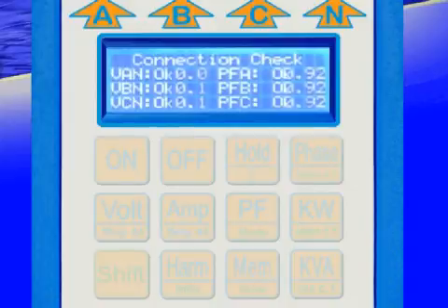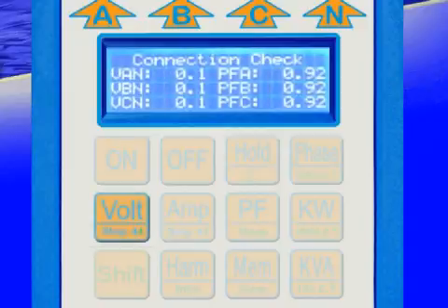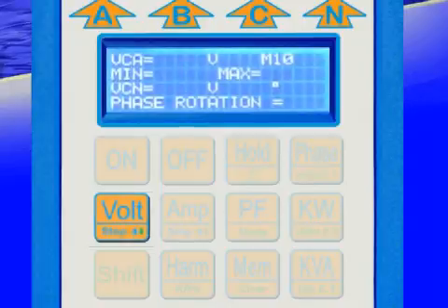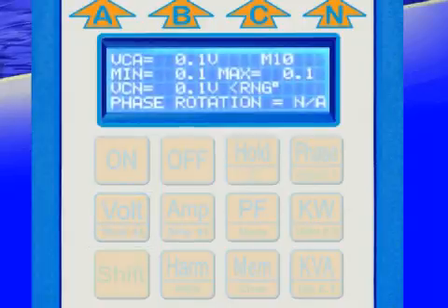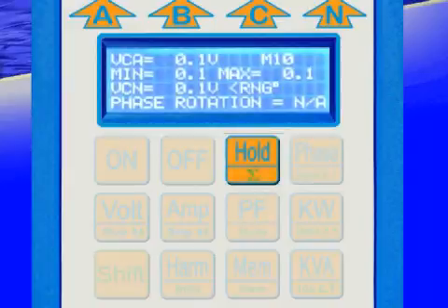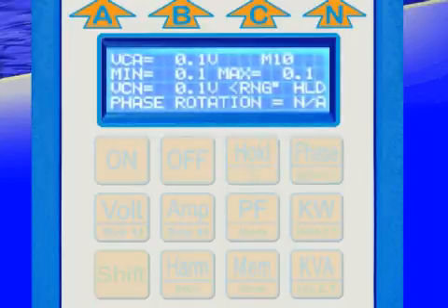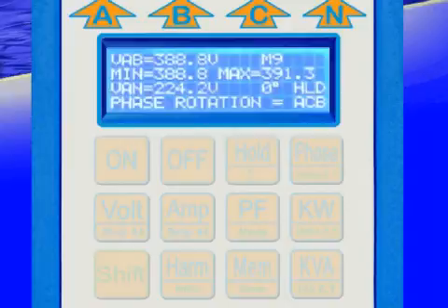When you are satisfied that all the connections you have made are correct, press and hold Volt until the volt measurement screen appears. At this time, you are taking measurements and you can press the button for different functions to view the calculated parameters of the load. When you are done taking measurements in the energy audit mode, press the hold button until you see the HLD indicator on the display. This indicator shows that the Harmonitor is no longer taking measurements and the last data that you sampled is safely stored in memory. It is important to note that you should always turn hold on before changing or removing CTs or voltage leads while sampling, or else the minimums and maximums that are saved in memory may not be accurate.